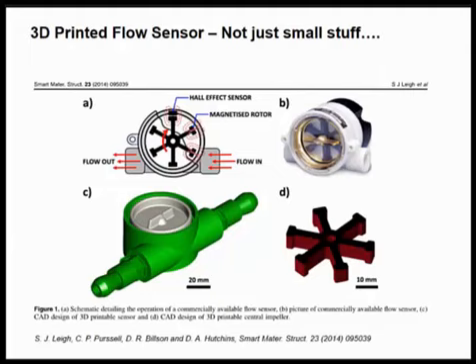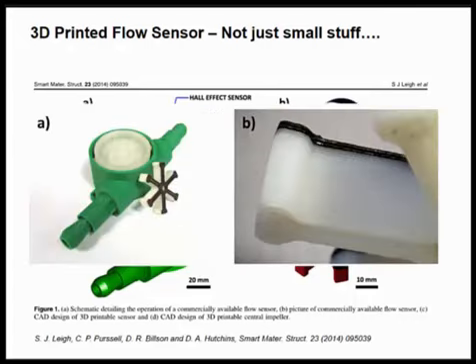Some more flow sensors. This time using FDM, so a thermoplastic technology. Again, magnetite nanoparticles embedded in a thermoplastic this time. Conventional commercial sensor uses a Hall effect sensor to sense the rotation of an entirely ferrous impeller. We copied, or imitated, this design and made our own impeller. Rather than make the whole of the impeller from the magnetite material, we just did 2 layers, about 200 microns on top. So the rest was thermoplastic and then just 2 layers of this functional material. So you can see the layers on top of the impeller.